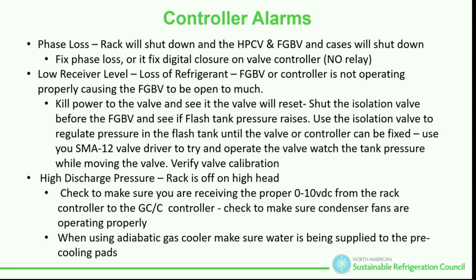So the flash gas bypass is not operating properly. It's open too much or closed too much. But I will see a receiver level low. That means it could be the valve is just open. It could be stuck. It lost its step; it's bipolar. I may have to grab my SMA 12 and drive it as I investigate whether it's the motor winding. Is it the motor winding? Look at the voltage. Look at the resistance across the windings. Try to drive it with your SMA 12. Make sure it's not shorted to ground. Make sure it's not shorted down. If I'm driving my SMA 12, how do I know if it's working or not?